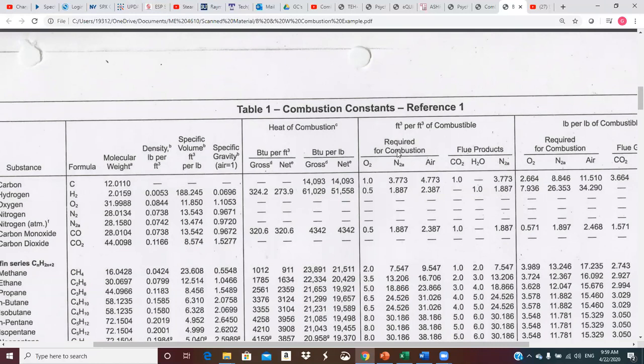We typically get the air from outside. To get one mole of oxygen O2, we have to also bring in 3.773 moles of N2A — which is everything else excluding water vapor. So you have to bring in 4.773 moles of air to get your one mole of oxygen. That also brings in 3.773 moles of N2A up the stack. The one mole of carbon combines with one mole of oxygen to give one mole of CO2, and then we also pass the N2A up the stack.